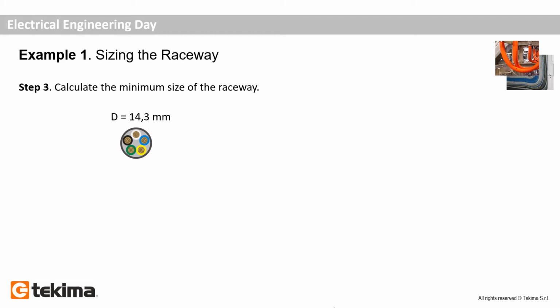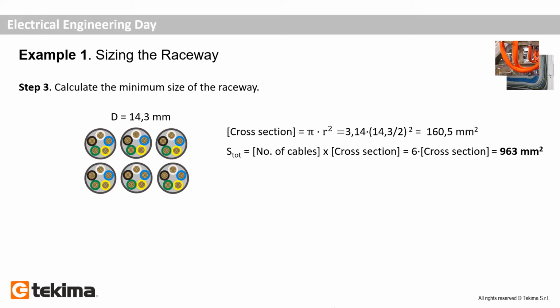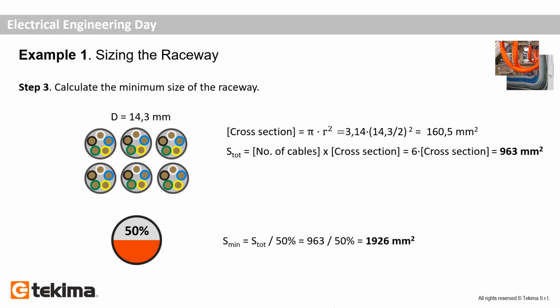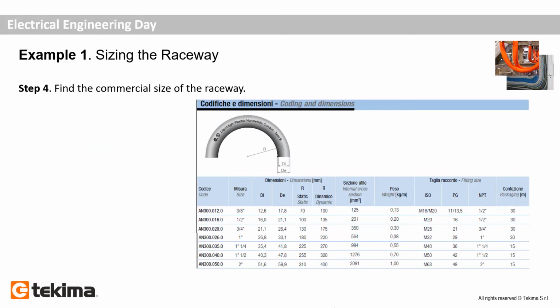To do that, we have to understand the total cross-sectional area occupied by the cables. For one cable, the cross-sectional area will be 160.5 square millimeters. That means that for 6 cables it will be a total of 963 square millimeters. With a percentage of 50%, we can understand the minimum internal area of the raceway that we have to look for. That means 963 divided by 0.5, which is 1926 square millimeters. We can now find the commercial size of the raceway based on the result obtained. The raceway that allows us to reach at least 1926 square millimeters is a 2-inch raceway.